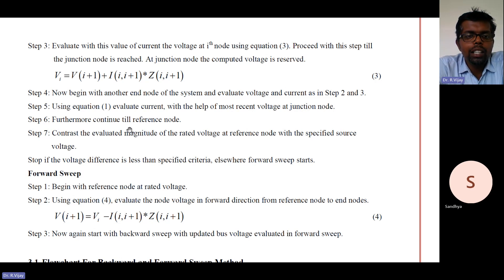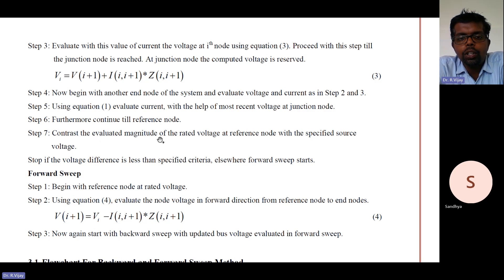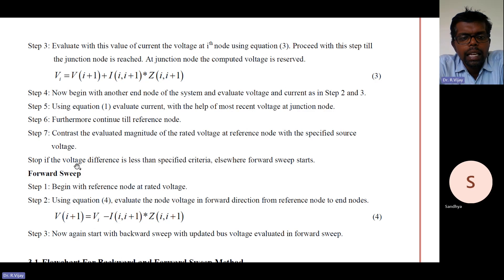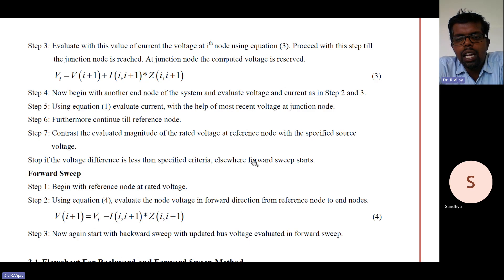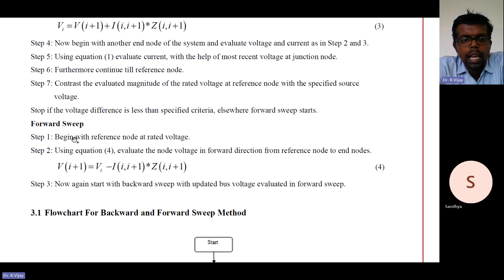Step 6: Continue till the reference node is reached. Step 7: Compare the evaluated magnitude of the voltage at the reference node with the specified source voltage. Stop if the voltage difference is less than the specified criteria; otherwise, the forward sweep starts. So if the voltage difference is less than the specified tolerance, stop; otherwise proceed to the forward sweep.